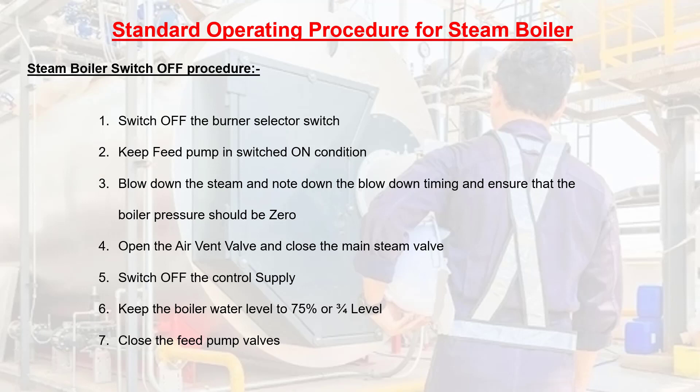Steam Boiler Switch OFF Procedure: Step 1: switch OFF the burner selector switch. Step 2: keep the feed pump in switched ON condition. Step 3: blow down the steam, note down the blowdown timing, and ensure that the boiler pressure reaches 0. Step 4: open the air vent valve and close the main steam valve. Step 5: switch OFF the control supply. Step 6: keep the boiler water level at 75% or three-quarters level. Step 7: close the feed pump valves.